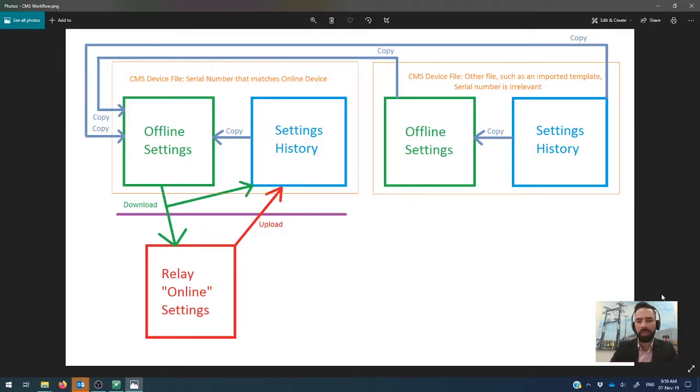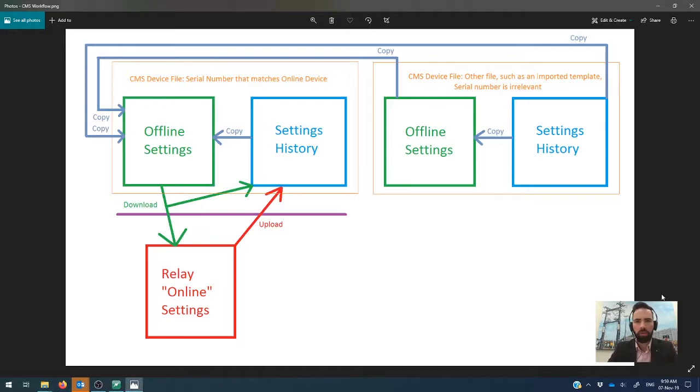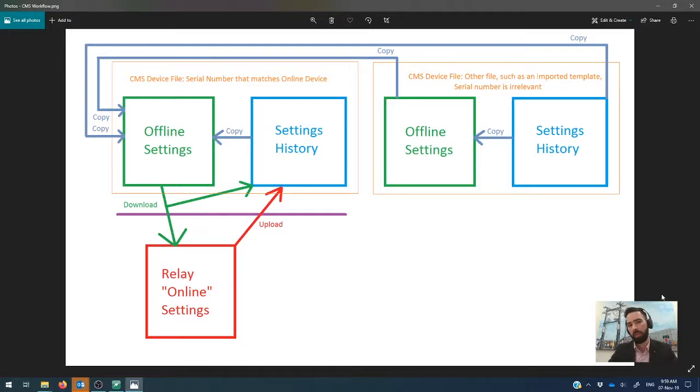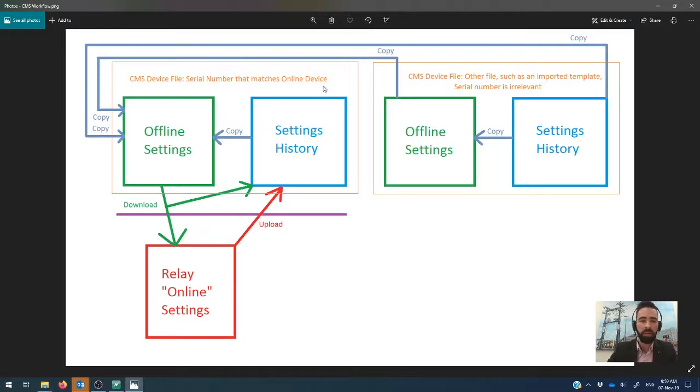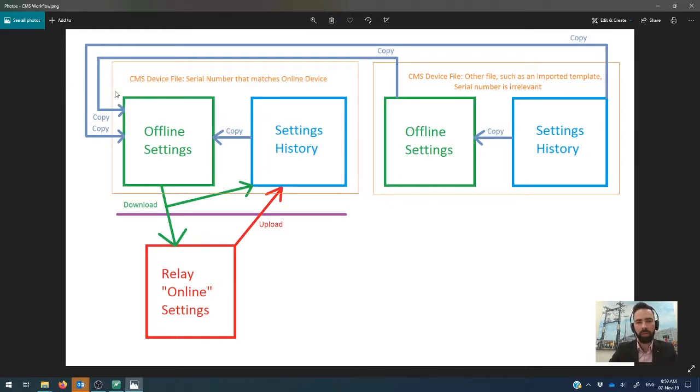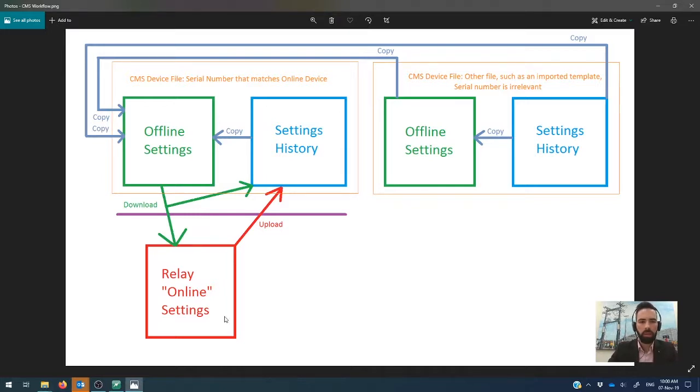But basically what it does is that CMS tries to keep a history of absolutely everything that you do. And the reason that we do that is so that if you ever need to go back to previous versions of the settings, then we've got a copy of that stuff ready for you to go. So in this box, the orange box here corresponds with CMS device files, specifically one where the serial number matches the online device. And in this case, because we're connected to a live device, we're working in this box here, and I've got a link to an online relay.